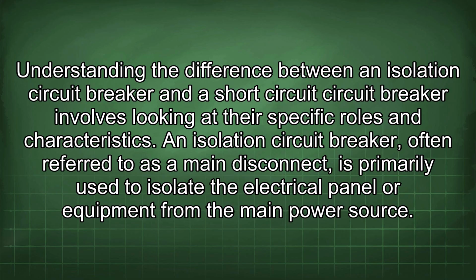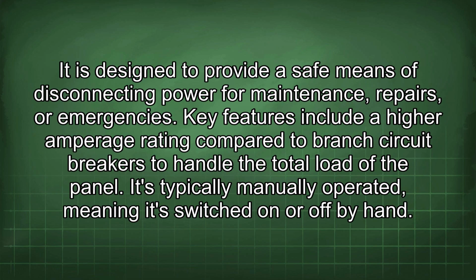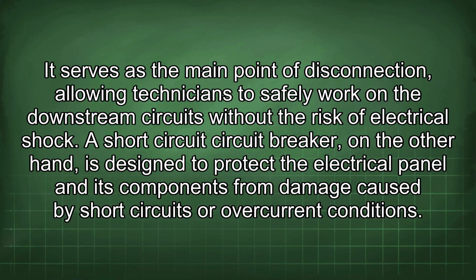Understanding the difference between an isolation circuit breaker and a short circuit breaker involves looking at their specific roles and characteristics. An isolation circuit breaker, often referred to as a main disconnect, is primarily used to isolate the electrical panel or equipment from the main power source. It is designed to provide a safe means of disconnecting power for maintenance, repairs, or emergencies. Key features include a higher amperage rating compared to branch circuit breakers to handle the total load of the panel. It's typically manually operated, meaning it's switched on or off by hand. It serves as the main point of disconnection, allowing technicians to safely work on the downstream circuits without the risk of electrical shock.